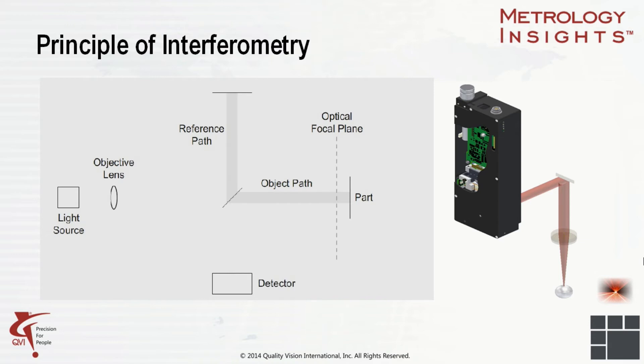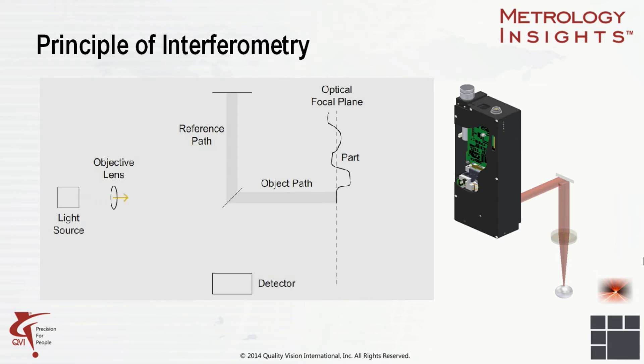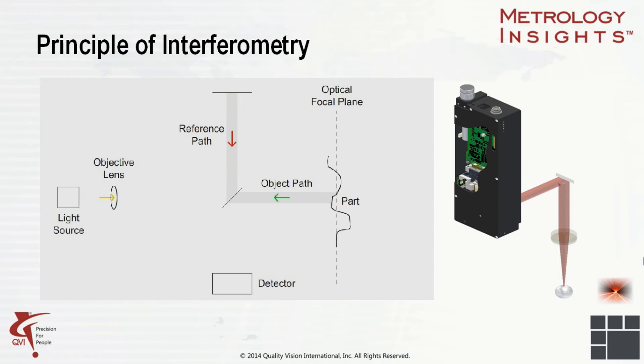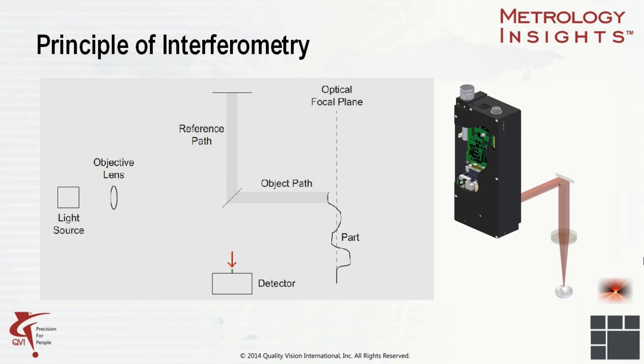Let's look more closely at the principles behind interferometry. A light source gets projected down onto the part, and then it is received back up as two opposite paths. Depending on the timing between when those signals are received, the detector can tell how far away it is from the part. Shown here, we are scanning a part. As the part moves further away, you see the arrows coming back to the detector at different times — sometimes the green arrow is first, and sometimes the red arrow is first.